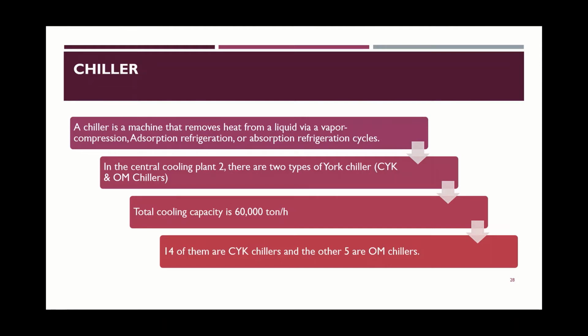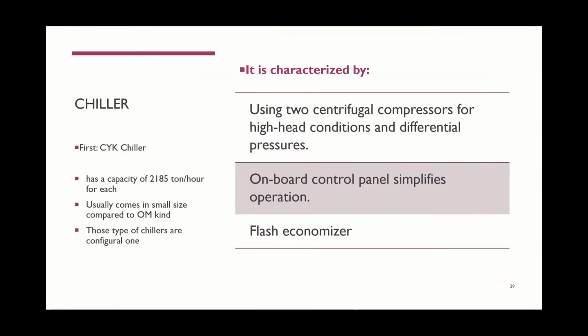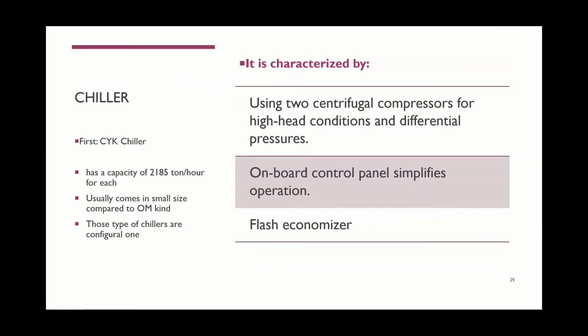In Central Cooling Plant 2, there are two types of York chillers: CYK chillers and OM chillers. The cooling capacity is 60,000 tons. 14 of them are CYK chillers and the other 5 are OM chillers. In the plant, there are 14 CYK chillers. This type of chiller has a capacity of 2,185 tons for each one. They usually come in a small size compared to the OM chillers. This type of chiller is centrifugal. It is characterized by using two centrifugal compressors for high-head conditions and differential processes. Also, it consists of a flash economizer. Also, the onboard control panel simplifies operation.